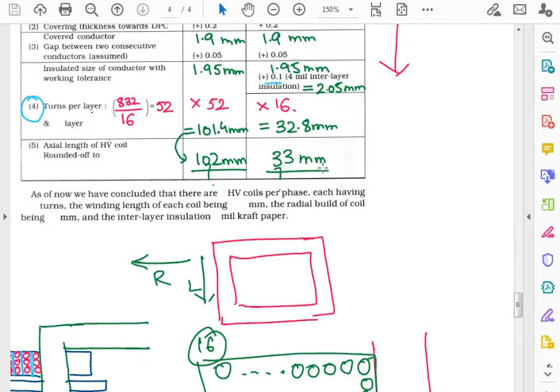Then there's the radial clearance between the core and the low voltage coil. This thickness comes in because when making a stepped core, in this case an 11-step core, it's not circular, it has sharp edges, so you put an asbestos or plastic cylinder on which you do the windings.